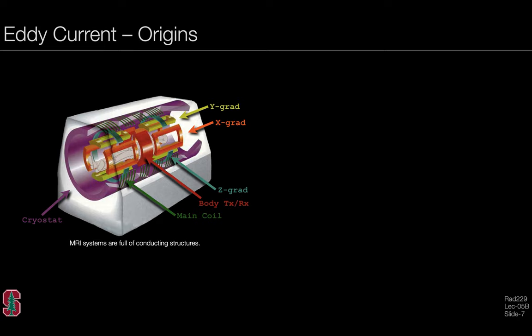The origins of eddy currents arise from the MRI hardware system. The gradient hardware, body transmit system, and main coil windings in the cryostat are among the essential components. The MR system is full of conducting metallic structures that can support currents, and currents running through a metallic structure generate a magnetic field. This is fundamentally the origin of eddy currents.